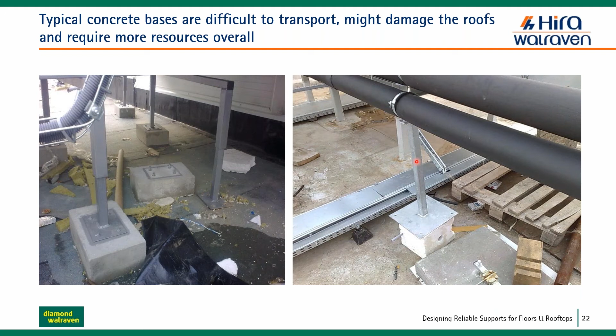Some other cases we see a lot at site are using incomplete blocks, hollow blocks as you can see here, and trying to fix pipe support or duct support on them, claiming that since it's lightweight it can take the load and it's not critical. Still, it is a critical solution to consider. This support should be studied carefully because it affects the lifetime of the project and of the service itself.